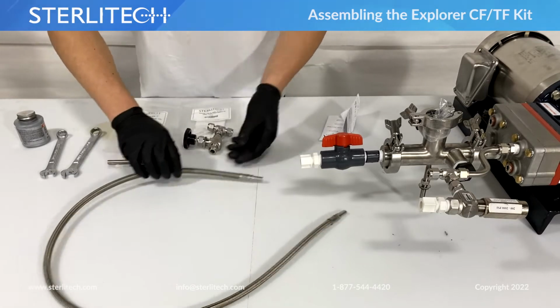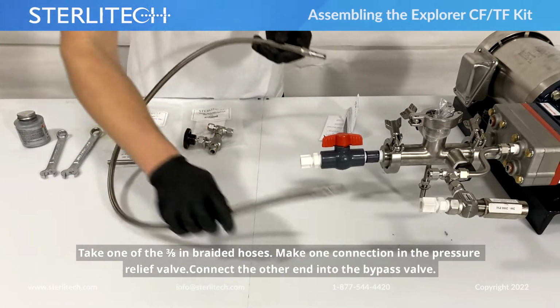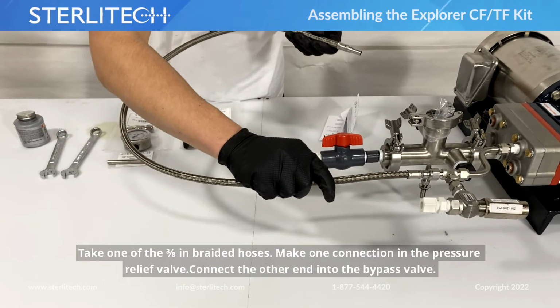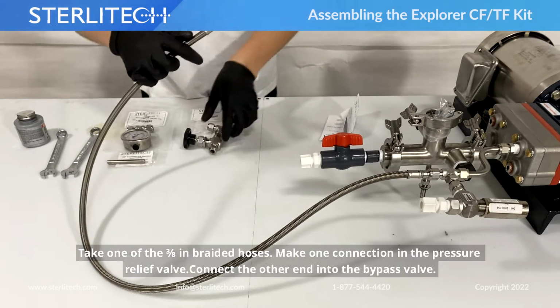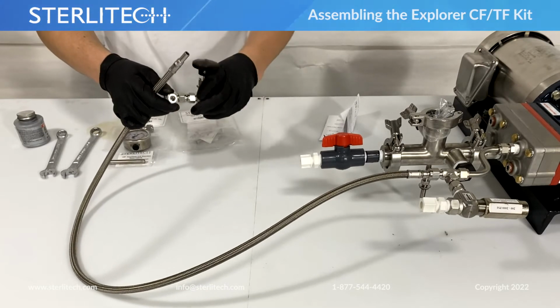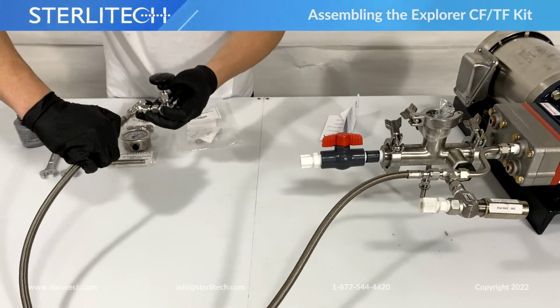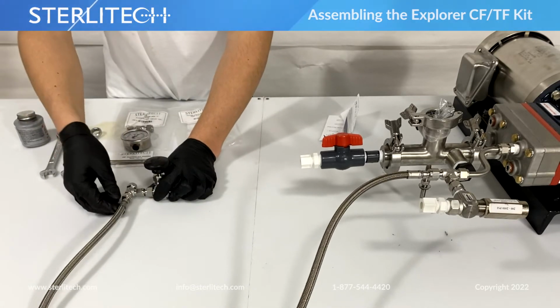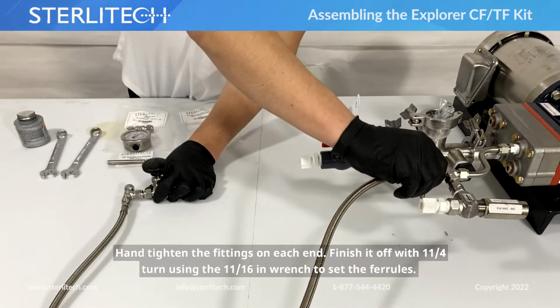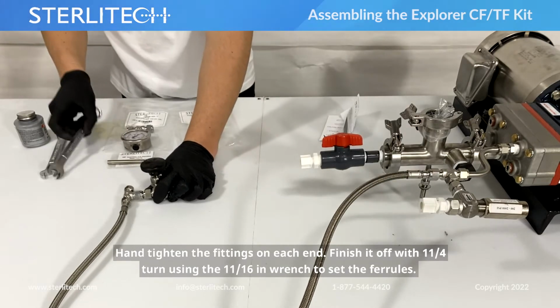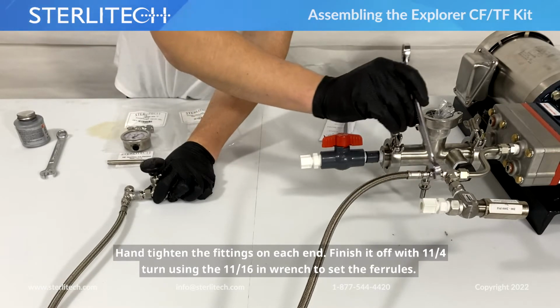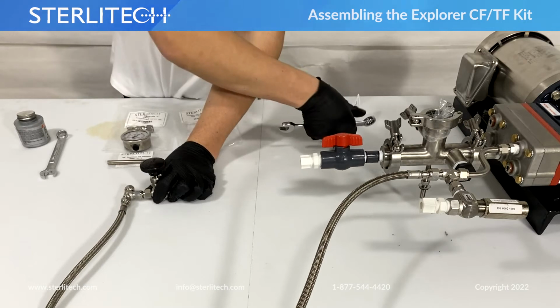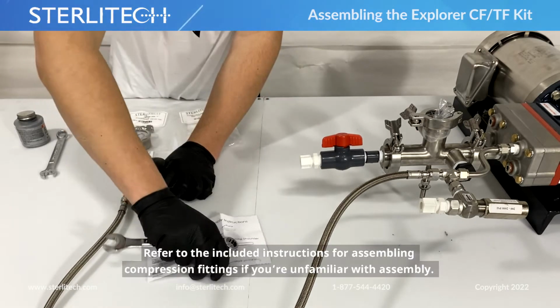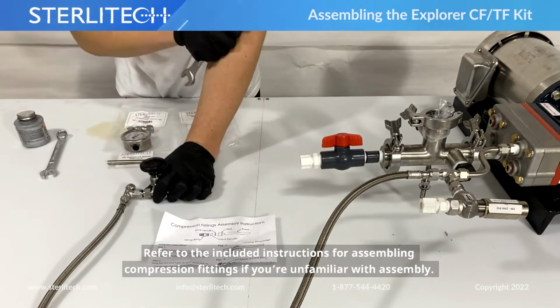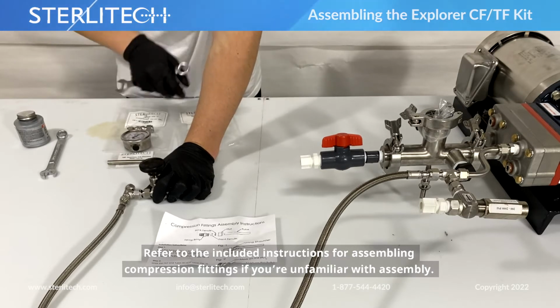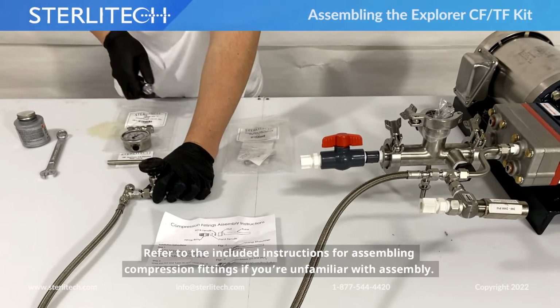From here, we're going to take a stretch of our 3/8 braided hose. We're going to make one connection in our pressure relief valve. The other end is going to connect into our bypass valve. Get the fittings hand tight on each end. And then we're going to finish it off with 1 1/4 turn using the 11/16 wrench to set the ferrules. If you're not familiar with how that works, these compression fittings come with an instruction sheet in each of those assemblies, so please take a look at that.